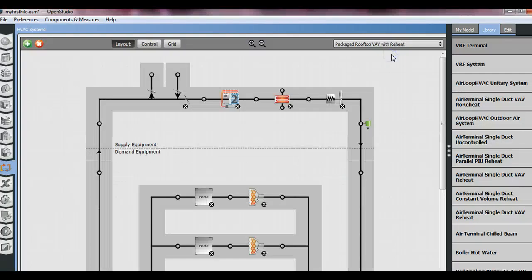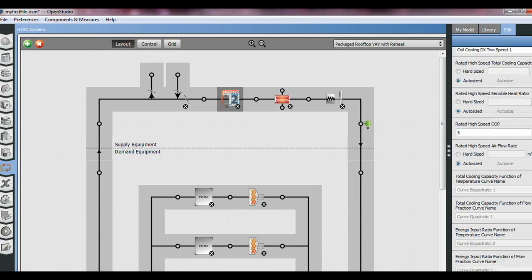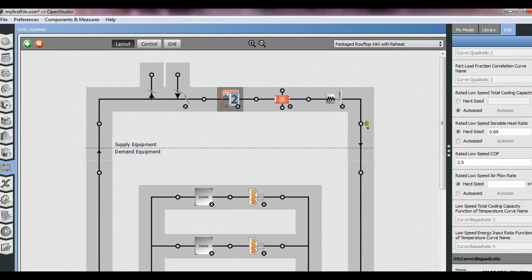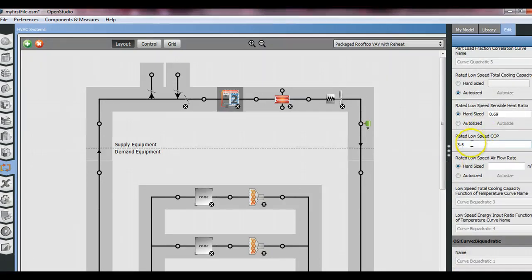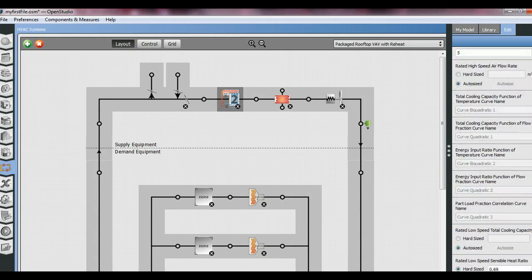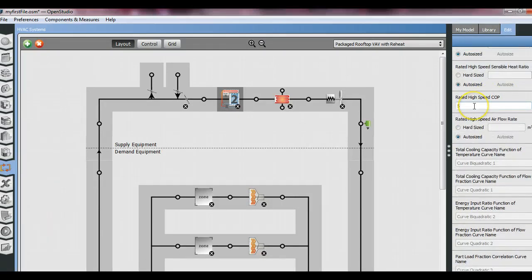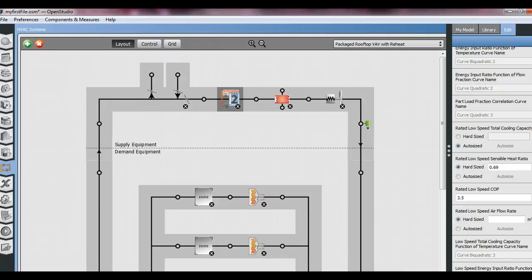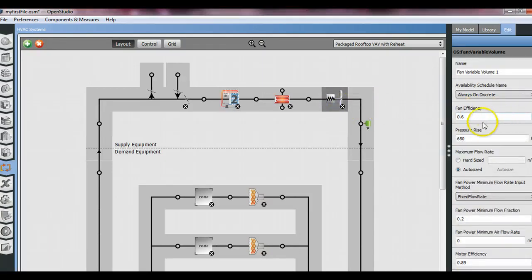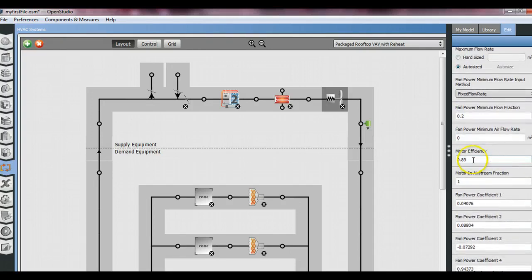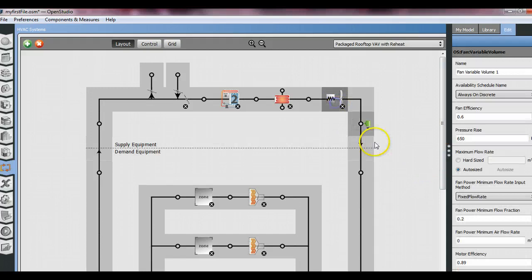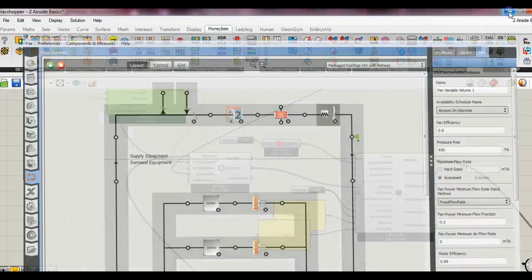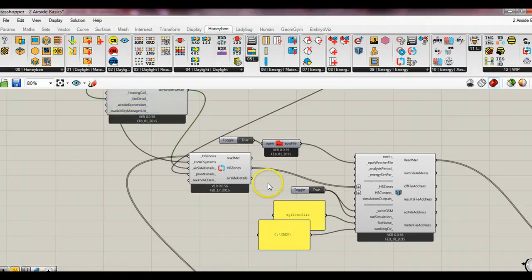If we come down here and look at our package rooftop system with VAV, and take a look at our coil, you can see that it has a rated low speed COP of 3.5 and a rated high speed COP of 5. So all these entries that we've provided have come across. The fan has a fan efficiency of 60%, a pressure rise of 650 as we specified, and a motor efficiency of 89.